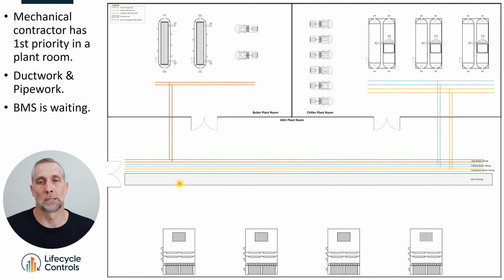So the first person that has priority is the mechanical contractor, and that's because a lot of the other electrical containment is usually installed off of pipework and ductwork. So on those threaded rods from the ceiling that come down that hold the pipework and ductwork, often we'll install our electrical tray or ducting off of those hangers. So we've got to wait.